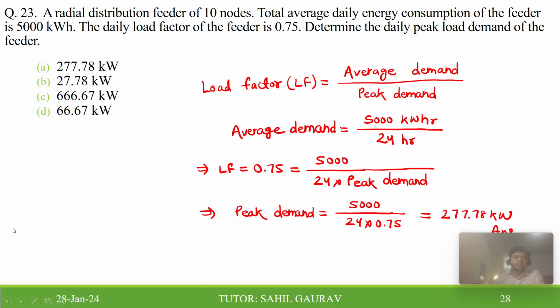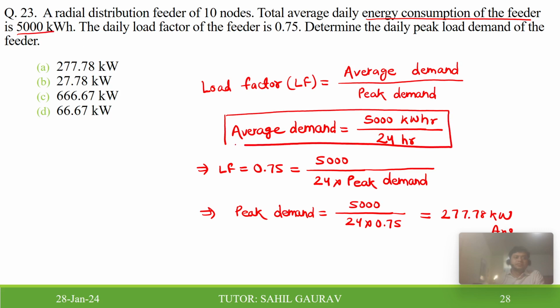Now the next problem: a radial distribution feeder of 10 nodes, and the total average daily energy consumption of the feeder is 5000 kilowatt hour. The daily load factor of the feeder is 0.75. Determine the daily peak demand of the feeder. We have solved many problems on load factor, so there is nothing new. The daily energy consumption is given as 5000 kilowatt hour. The average demand is 5000 kilowatt hour divided by 24 hour, which gives a power value, and the load factor is given as 0.75. So you can find the daily peak demand, which comes as 277.78 kilowatt. Option A is correct.